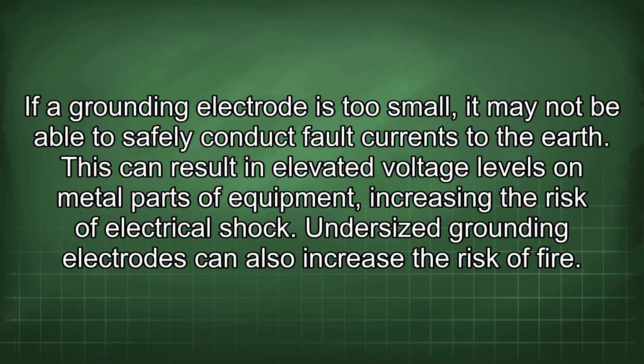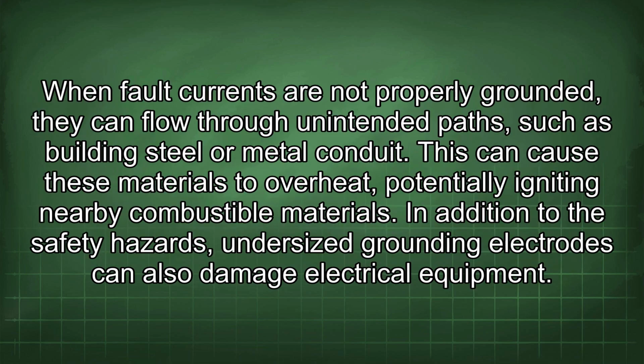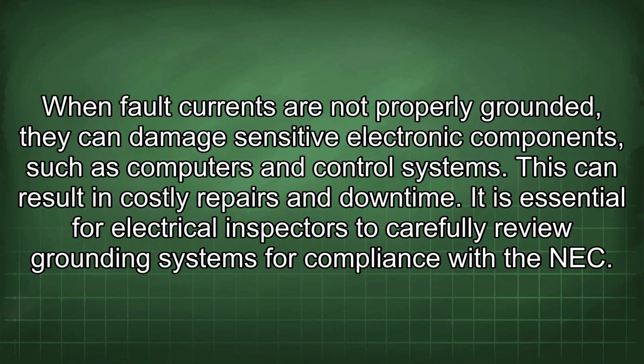Undersized grounding electrodes can also increase the risk of fire. When fault currents are not properly grounded, they can flow through unintended paths, such as building steel or metal conduit. This can cause these materials to overheat, potentially igniting nearby combustible materials. In addition to the safety hazards, undersized grounding electrodes can also damage electrical equipment. When fault currents are not properly grounded, they can damage sensitive electronic components such as computers and control systems. This can result in costly repairs and downtime.